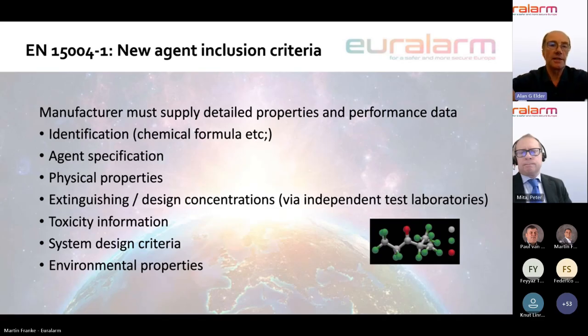So the next topic is the clauses. It's actually contained in a new annex. It's Annex J of the standard. This is a normative annex, which basically means it must be followed. And so when a manufacturer of a new agent offers that agent up for inclusion in the standard, in the past, I'm not saying it was totally ad hoc, but I would say that there were certain criteria that the manufacturer needed to supply, but it wasn't nailed down as much as it perhaps should have been.